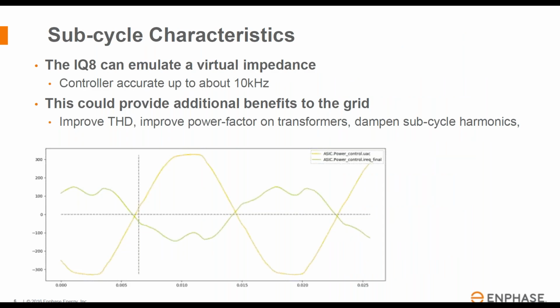The system has sub-cycle characteristics, which means it's adjusting the voltage and current many times per cycle on the utility grid. Right now, the controller in the IQ8 is accurate up to about 10 kilohertz, and above that it's essentially going to appear like its output filters, which are tuned to 10 kilohertz. So anything below 10 kilohertz, we can essentially change the shape of the voltage and current waveform as needed. We can adjust harmonics, we can adjust power factor, we can dampen sub-cycle harmonics. All of that is possible, which can all be potential benefits to the grid moving forward. Next slide, please.